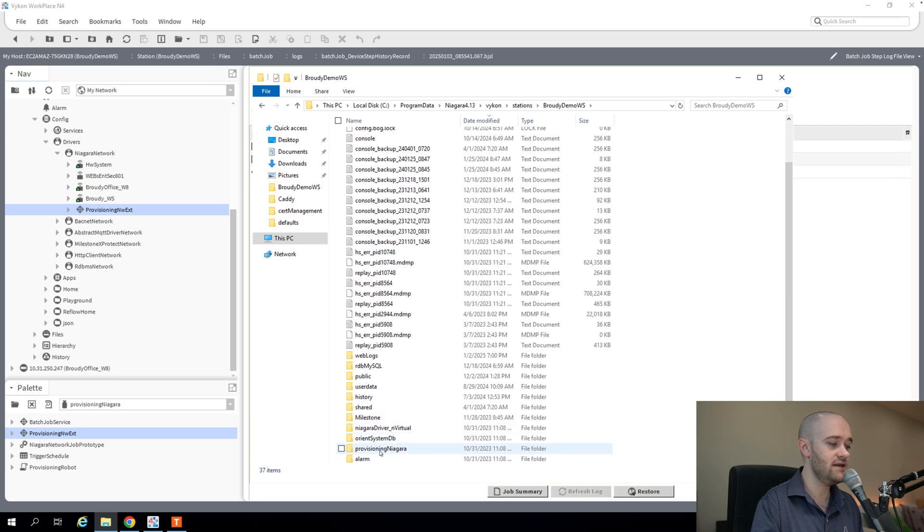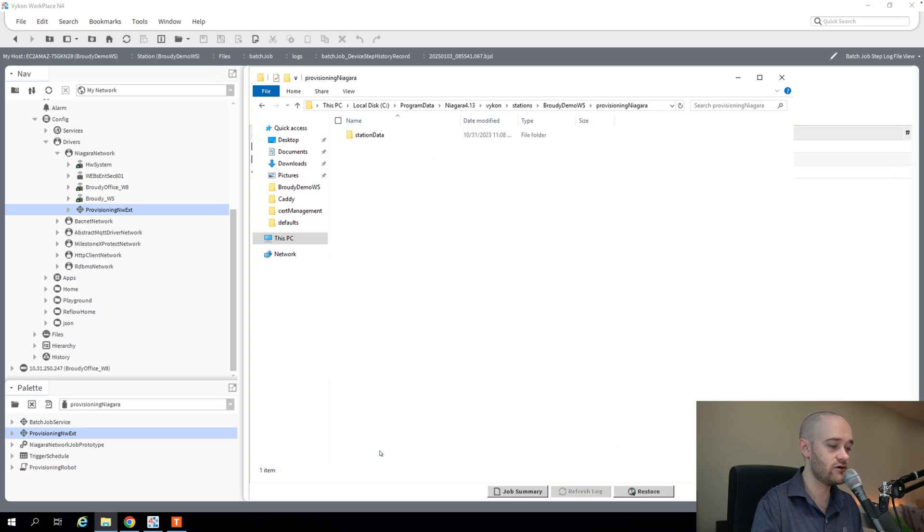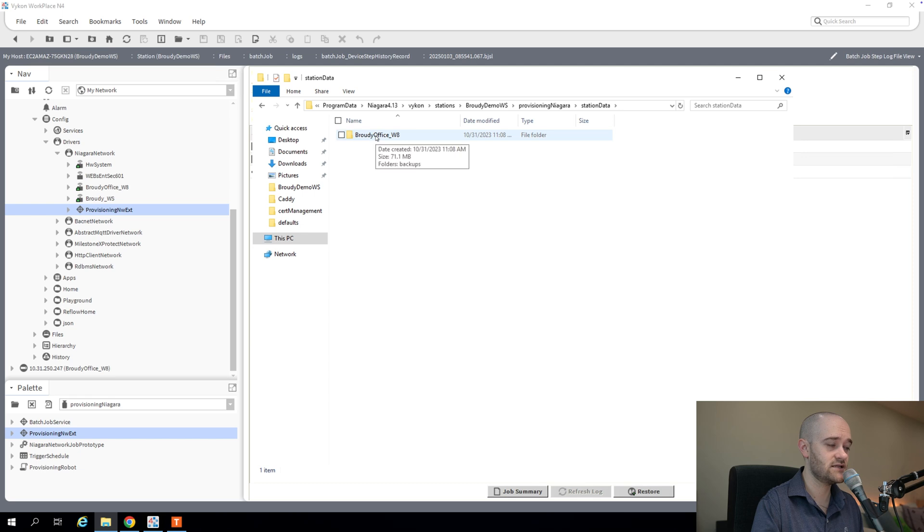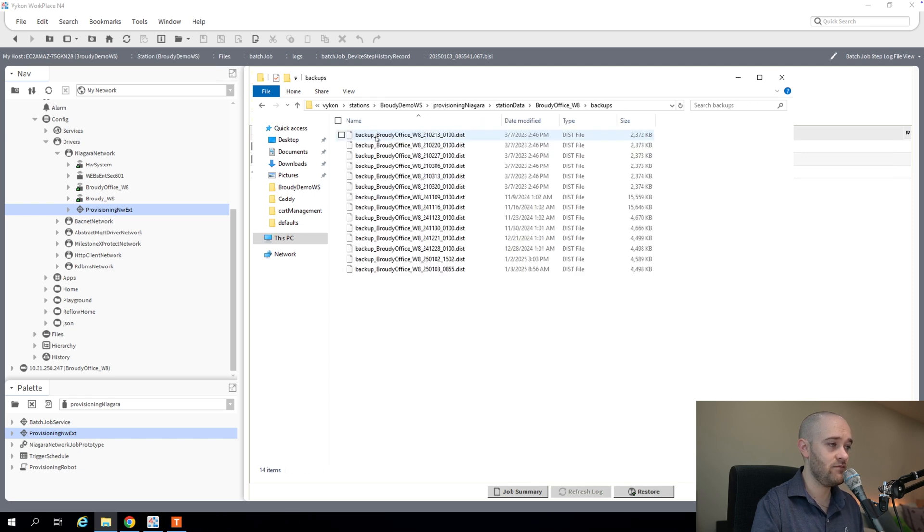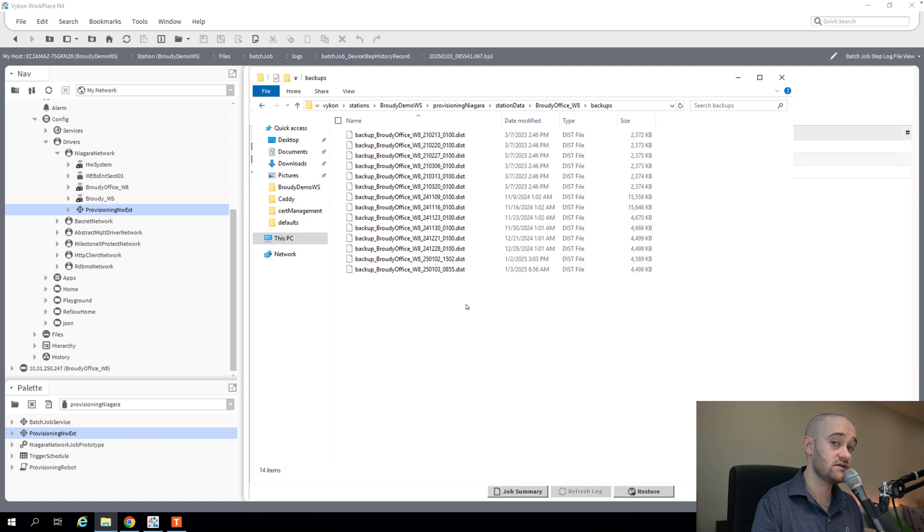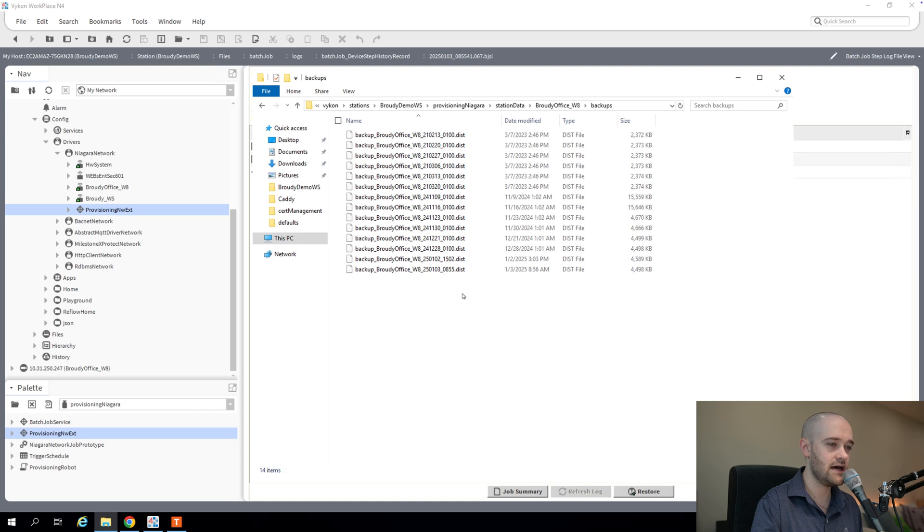This would be considered our protected station directory. And in that, we can see that we have a provisioning Niagara folder now. And in that, we have some station data. And then we have our individual stations. So in my case, I have my Broudy Office. And then in that, we have a backups folder. And then we have all of our backups that we've done through provisioning are kept here. We can do some work to make sure that we don't overload this directory with too many backups. We'll see that in a little bit here. But for now, this is where those files are going to live.